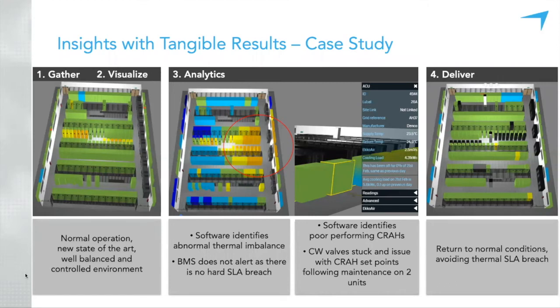As it turned out, the problem with these particular units was they'd undergone a maintenance which had reverted their set points to factory set point, but it's only 2 degrees different from the normal operating condition. And of course, under those conditions, there was no fault from those units. They were working perfectly normally. So it was a really helpful output for our customer to see that ahead of time before any SLA breaches happened.